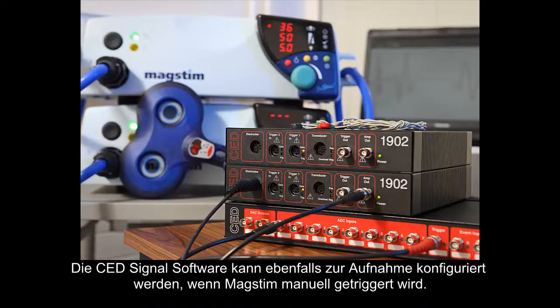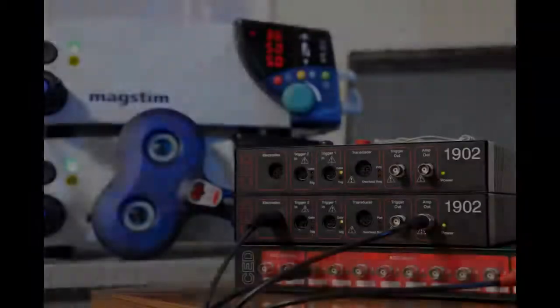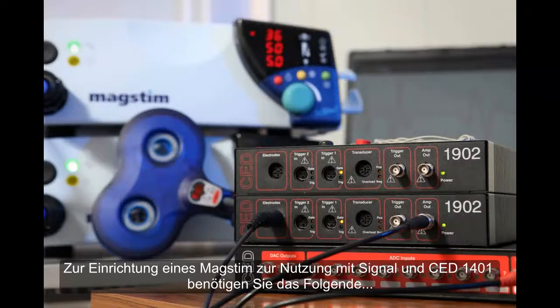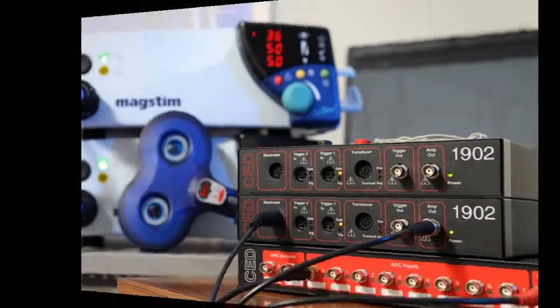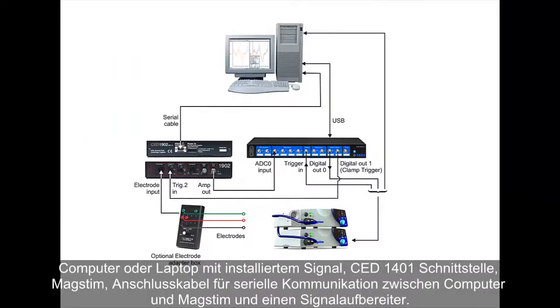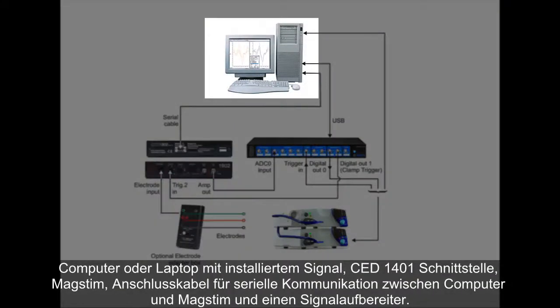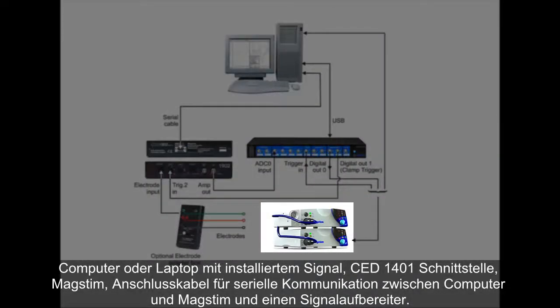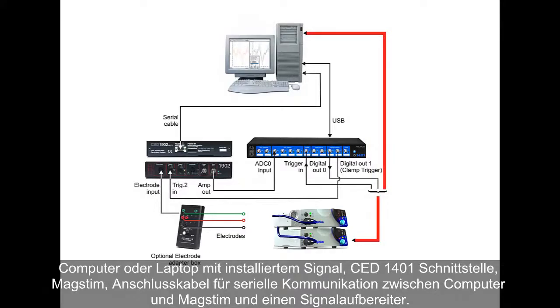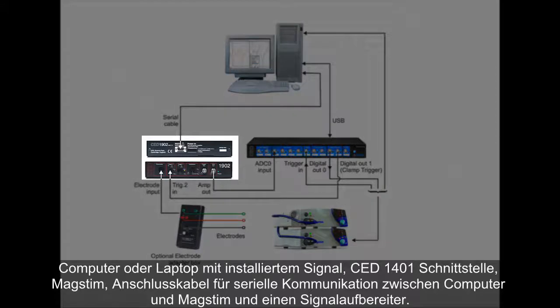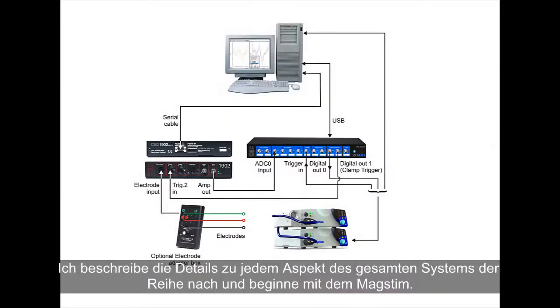CED signal software can also be configured to record when the MagStim is triggered manually. To set up a MagStim for use with signal and a CED1401, you will need a computer or laptop with signal installed, a CED1401 interface, a MagStim, a connecting cable for serial line communication between the computer and the MagStim, and a signal conditioner. I will describe details of each aspect of the whole system in turn, starting with the MagStim.